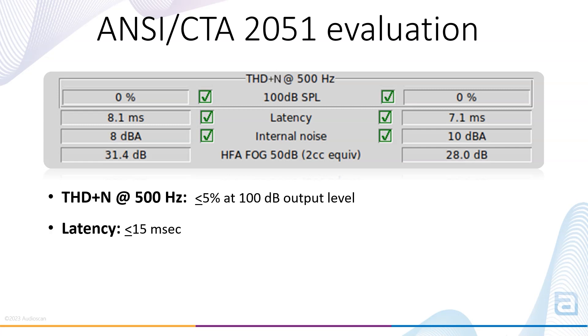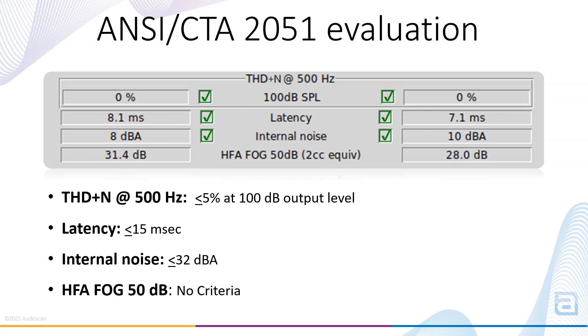Latency measures delay due to hearing aid processing, which can cause an undesirable misalignment between hearing aid processed sound and direct sound; devices must not exceed 15 ms of latency. Internal noise measures device-generated noise that may mask desirable sounds — testing should be completed with noise-floor-lowering processing such as auto-muting or downward expansion turned off, and results should not exceed 32 dB. High-frequency average full-on gain uses a 50 dB SPL pure tone to measure the output with gain set to maximum; the result is transformed from 0.4 cc and reported as a 2 cc equivalent value, with no pass/fail criteria for this measurement.